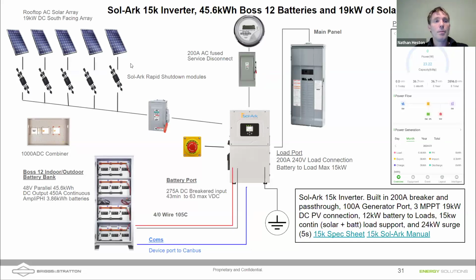I'm showing bringing in DC coupled solar here with Sol-Ark rapid shutdowns and a disconnect for the solar. You technically don't need this disconnect because the inverter has one built on the side of it. Rapid shutdown here is for shutting the inverter off in an emergency. This should be easily accessible in the event of an emergency, so we can shut those loads off, and that will shut the panels down at the rapid shutdown module level. Battery bank coming in, communications ports have to be wired in.